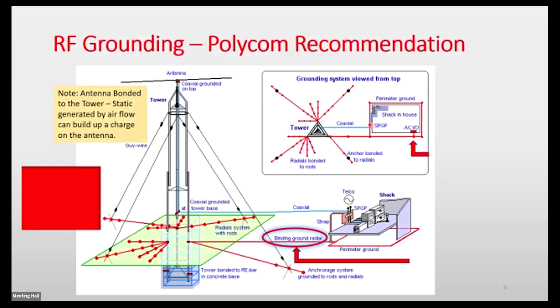Polyphaser is a company that makes grounding equipment and surge suppression equipment on the commercial industry side. You'll see it listed quite often. This is a drawing directly from them, and you'll see all those little red dots. Those are all ground rods placed in the ground around a tower to try to get the mass of the earth connected as much as possible, to get that resistance down and get a good mat for the grounding signal.